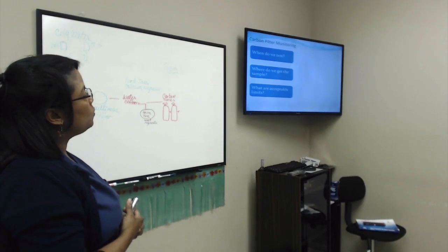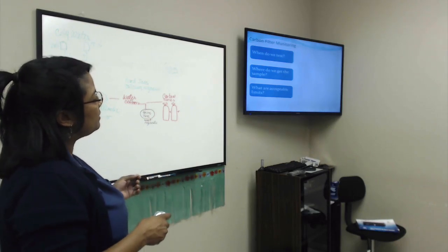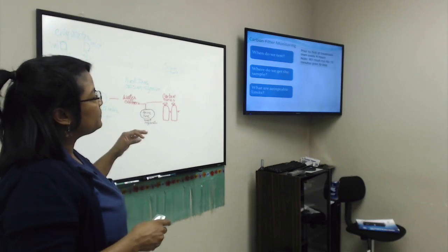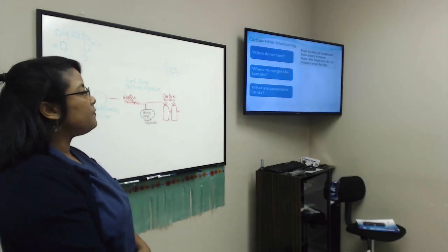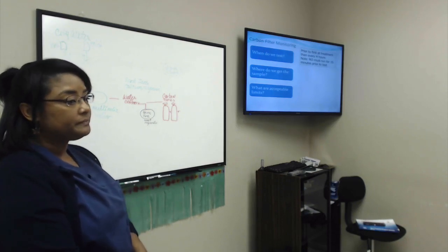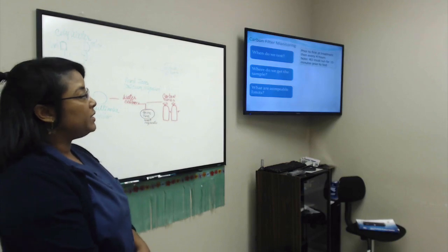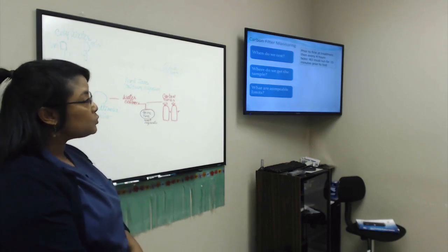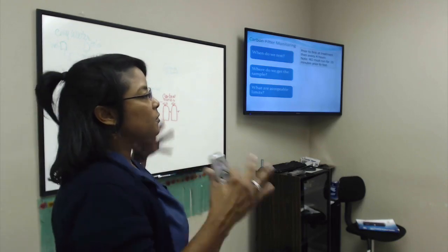So the carbon filter monitoring, how do we monitor them? We test them prior to the first patient, and then every 4 hours, okay? And the RO, in the morning, must run for 15 minutes prior to the test. So what are we testing?